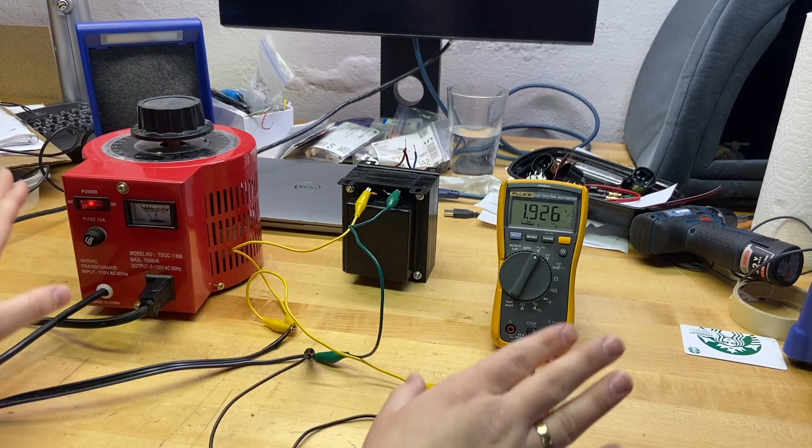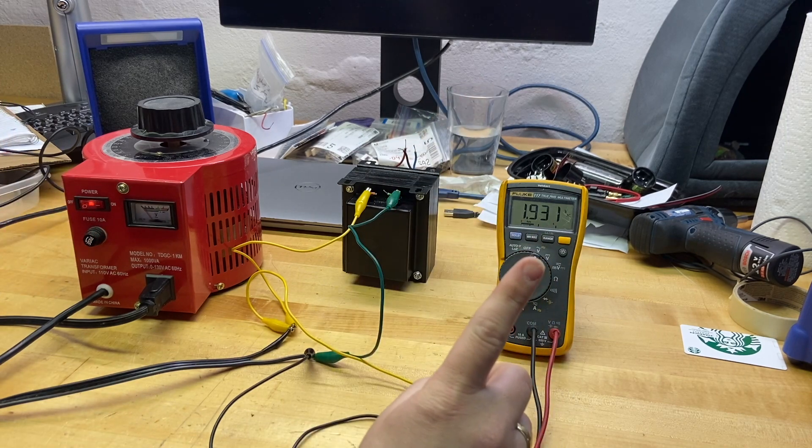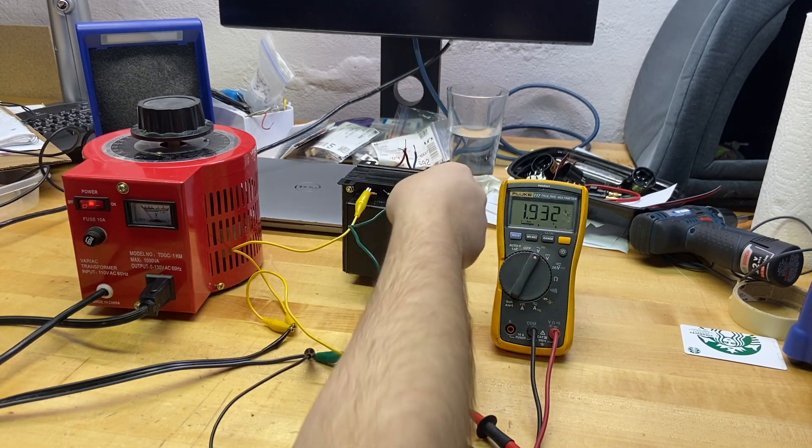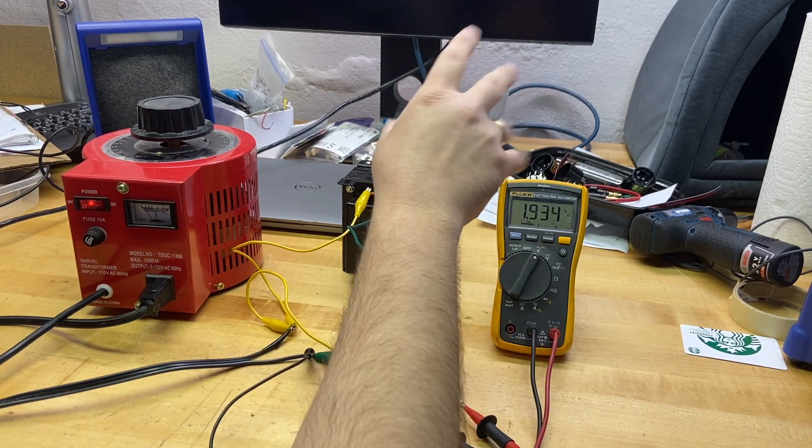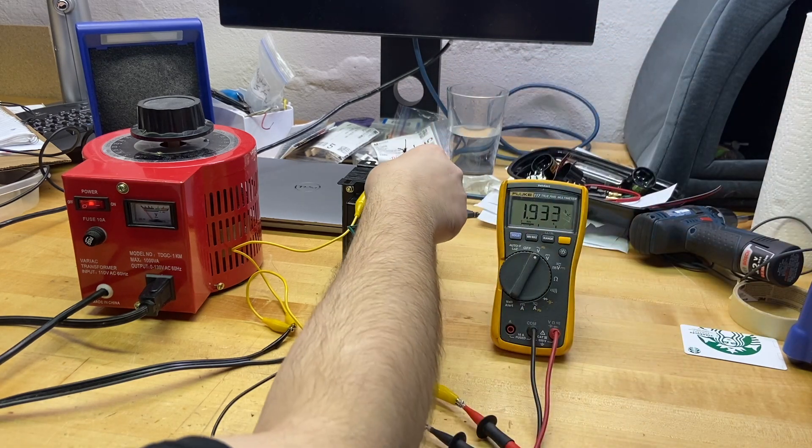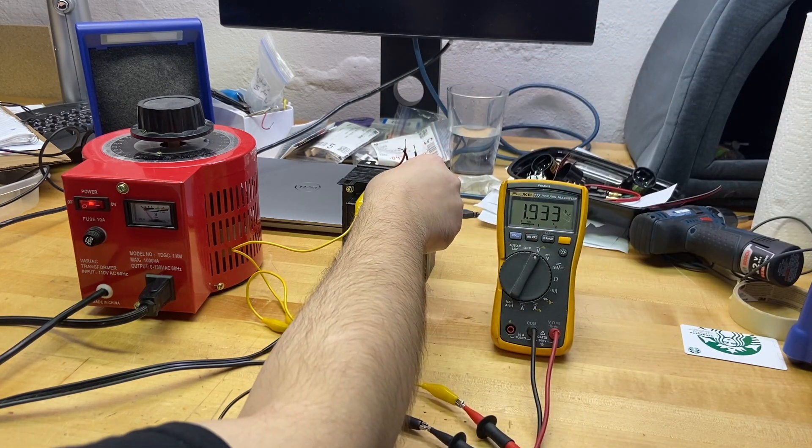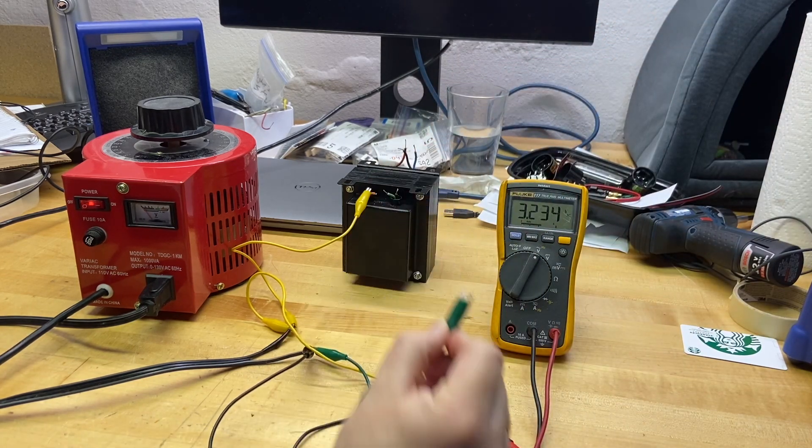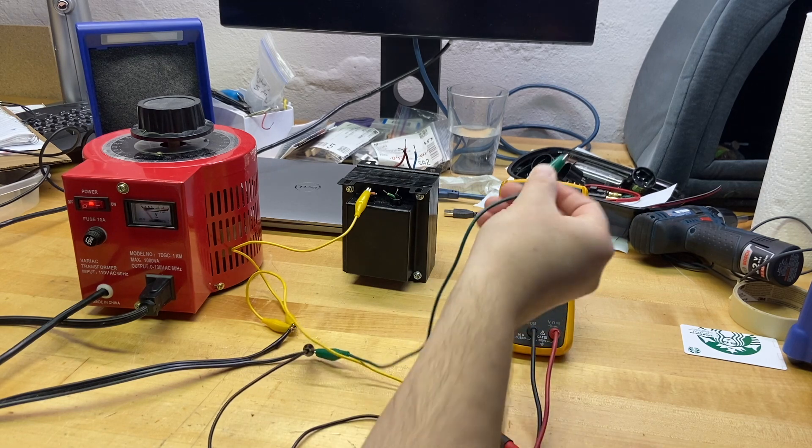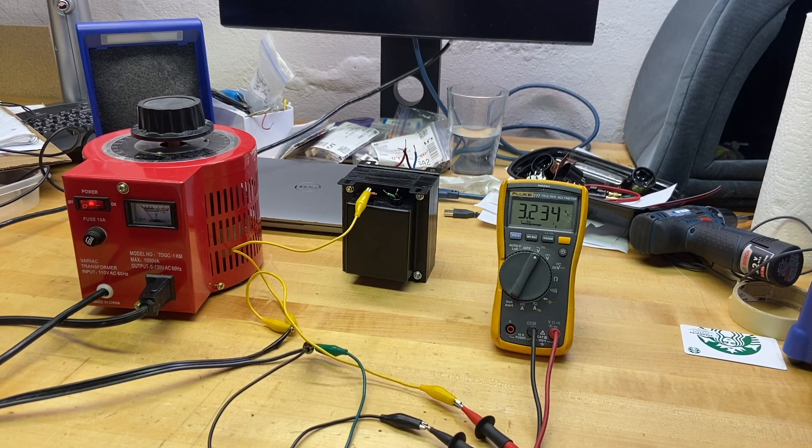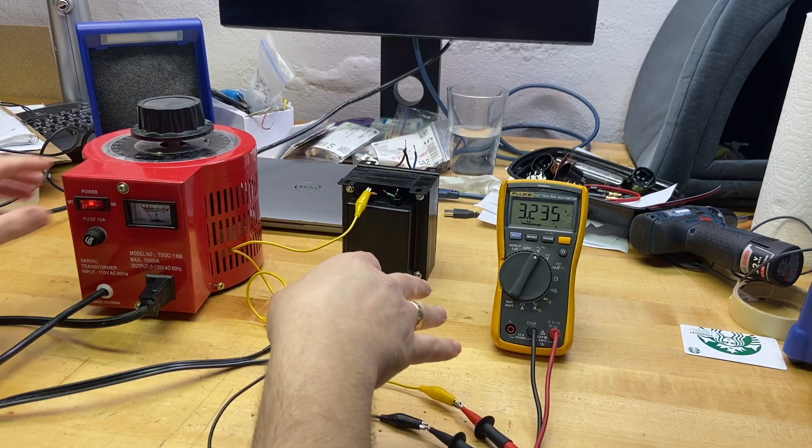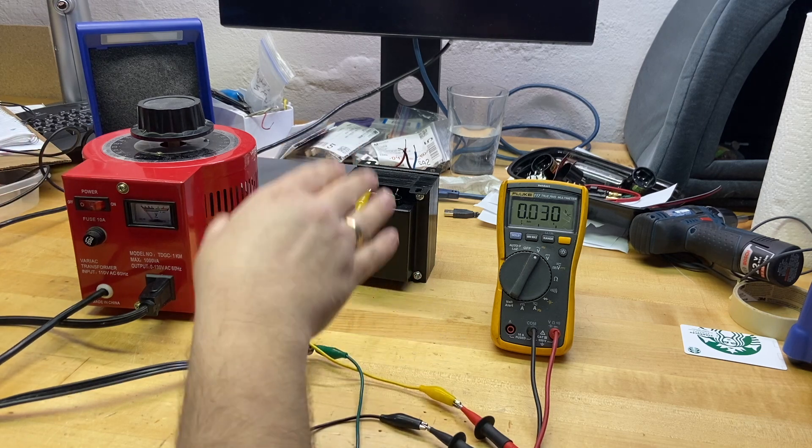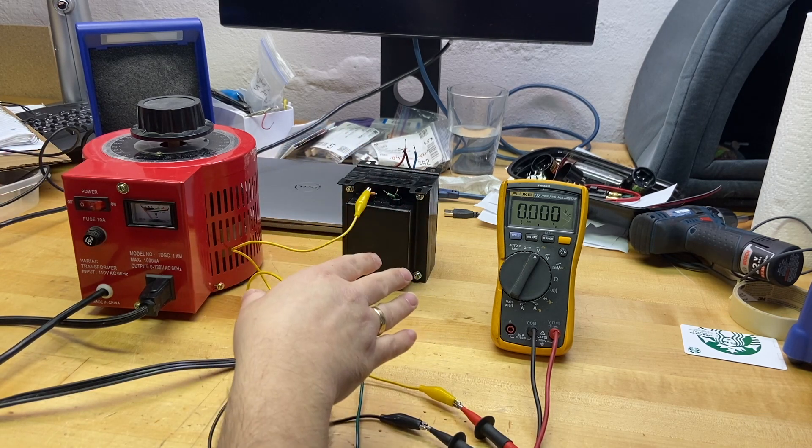And while it's hot, I can actually unhook some things and demonstrate this for you. So this is our common wire. So just very carefully, one hand, I'm going to reach in here and just grab it, open it up, let off of it, bam, 323.5 volts AC. We're right back. So you can see this transformer, definitely bad, and pulling current.